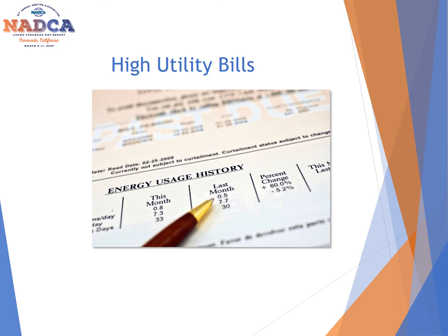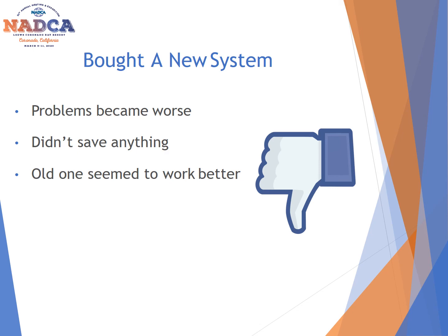less maintenance, and obviously spending less electricity. What ends up happening when somebody's house or their building is not cooling the way they want it to, the first reaction is, I need a new system. So you go out there and you buy a new air handler, you buy new condensation coils, and you buy a new condenser, and you put it in, and then the comment is made, it still has the same problem. You didn't fix it, and in some cases, the old system was working better. And that is because it's not the unit that is the problem, it's the ductwork.